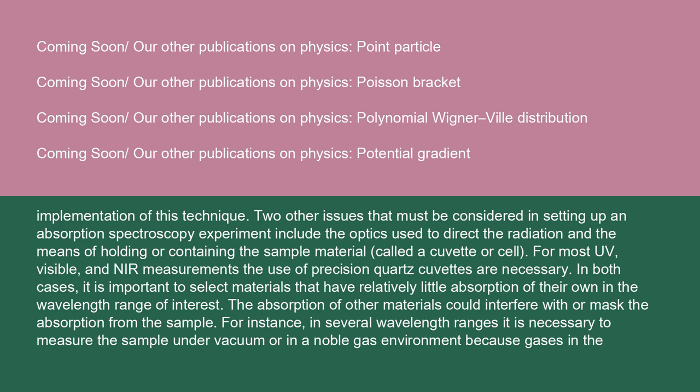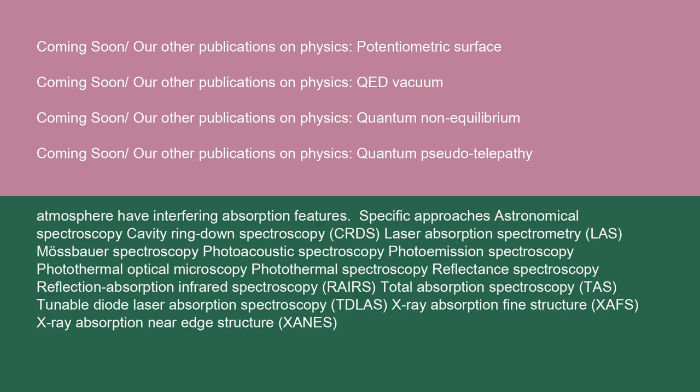Two other issues that must be considered in setting up an absorption spectroscopy experiment include the optics used to direct the radiation and the means of holding or containing the sample material, called a cuvette or cell. For most UV, visible, and NIR measurements, the use of precision quartz cuvettes is necessary. In both cases, it is important to select materials that have relatively little absorption of their own in the wavelength range of interest, as the absorption of other materials could interfere with or mask the absorption from the sample. For instance, in several wavelength ranges it is necessary to measure the sample under vacuum or in a noble gas environment because gases in the atmosphere have interfering absorption features.